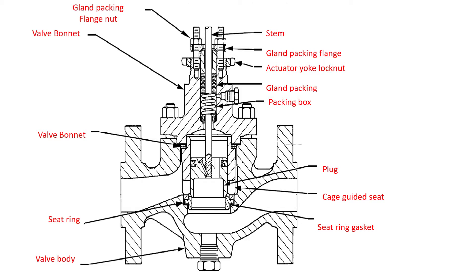Next we have the valve bonnet. The bonnet is a major pressure-containing component; it is bolted or threaded onto the valve body. It locates and guides the valve stem and also includes the bore for the packing — that is the gland packing. The bonnet also includes a yoke, which is used mainly to mount the actuator. This is the valve bonnet.